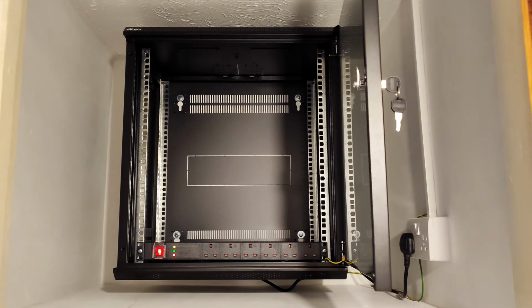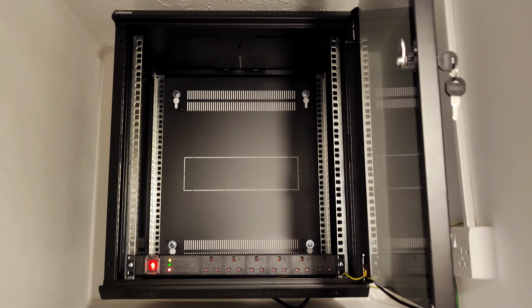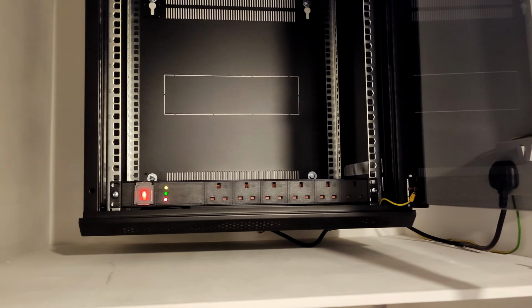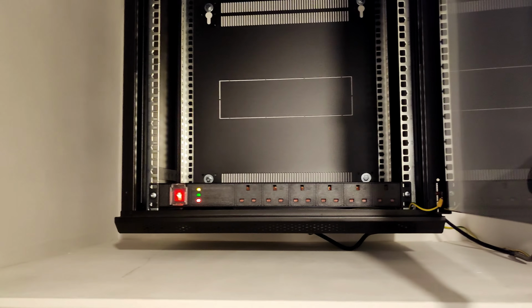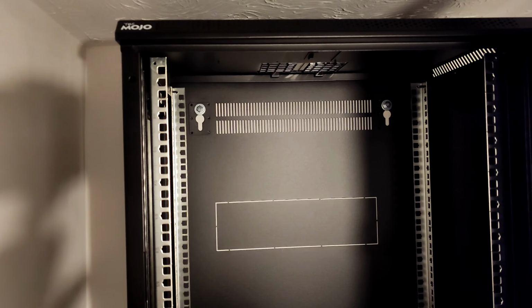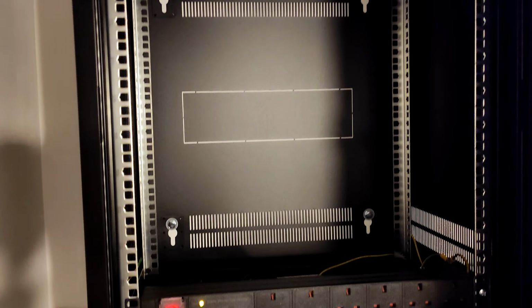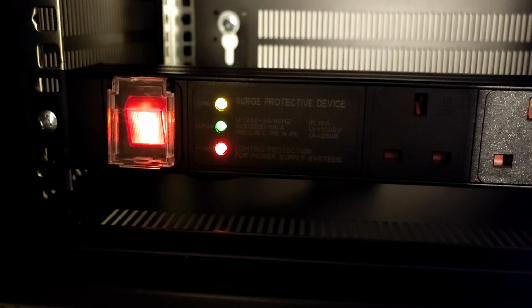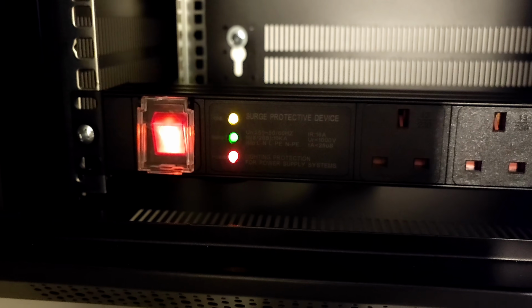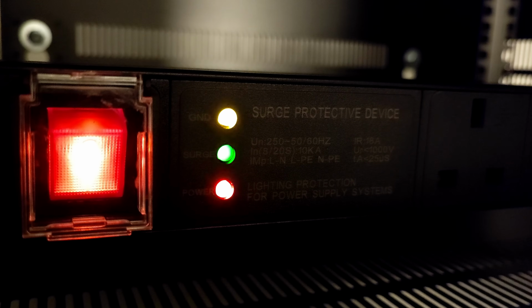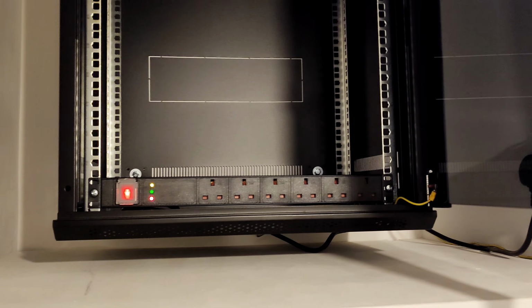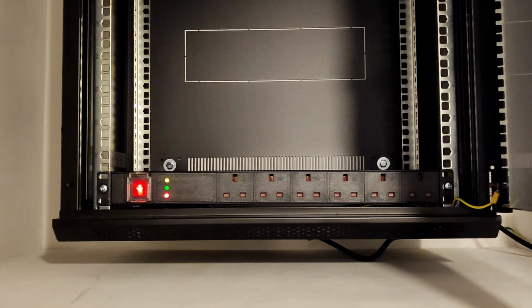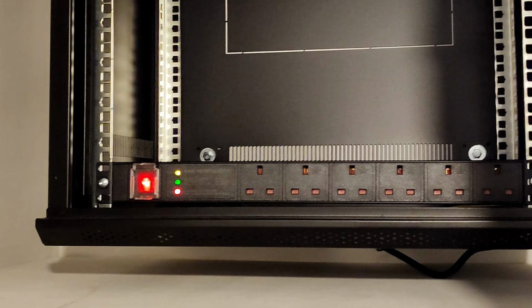My PDU is from LMS Data. It's not just a regular power distribution unit. This ensures that any excess energy is safely dissipated and protects your equipment from unexpected spikes, reducing the likelihood of damage or data loss. This PDU includes a dedicated grounding option, which contributes to the overall grounding strategy by ensuring that every device connected is safely and effectively grounded. An integrated status LED provides an instant visual confirmation that the unit is properly grounded as well. Each outlet is designed with surge protection. If there is a power surge, the PDU absorbs and dissipates the excess energy.